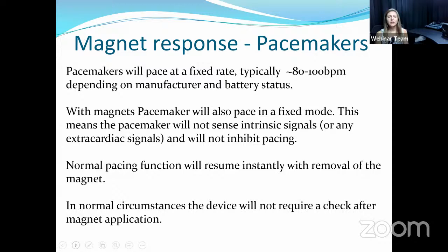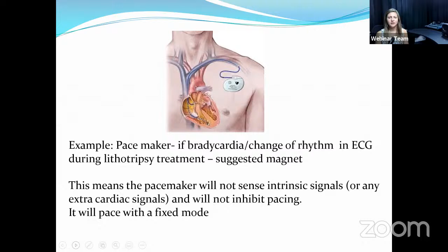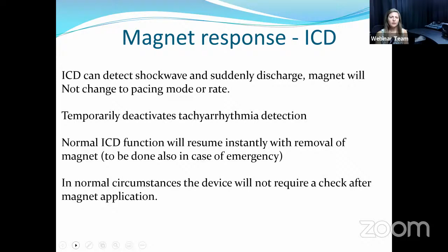And this can happen. It doesn't mean that we need to use a magnet all the time that there is a patient with a pacemaker. But actually, it's very important in this case to monitor the patient's rhythm with a simple ECG lead. And if we see a case of bradycardia, then we're going to use a magnet to stop the pacemaker from sensing the interference. For the defibrillator, this is even more important because the magnet can stop the defibrillator from detecting possible tachyarrhythmias, and therefore the defibrillator will not work while the magnet is in use and will resume its normal work as soon as the treatment is finished, or of course in case of emergency.